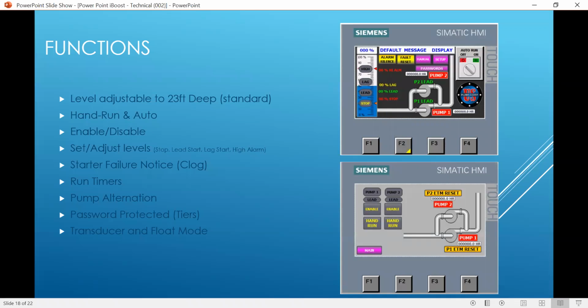Now, if it's just an auto reset, you can try to reset it from your computer screen without ever going out to the location. If the system starts running again and the pump doesn't go down, then you're done fixing your problem. If the pump is actually out, it's going to tell you that you've got a pump out or a pump clogged, and you're going to need a service person to go out there. So this is, we feel, the future of sump and sewage control. We think down the road, the HOA lights and the HOA panel for sump and sewage are going to go bye-bye, other than really small locations where they don't want to spend the extra expense.